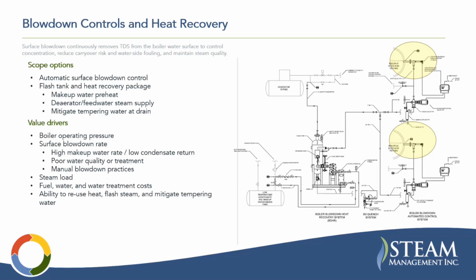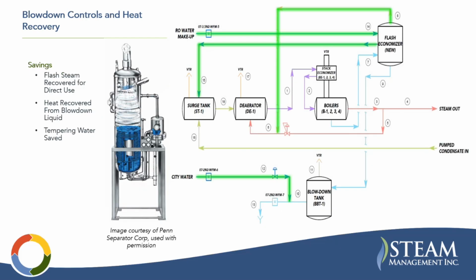And then once you determine your blowdown rate, that's generally expressed as a percentage of steam or feed water. Obviously, the larger the boiler is, say if the blowdown rate is 3%, the larger the boiler is, the higher that blowdown stream energy content is. And then, like any scopes, your fuel, water, and water treatment costs are going to drive the value of that energy and water that you're trying to save. The ability to reuse heat, flash steam, and mitigate tempering water are important, which I'll talk about here.